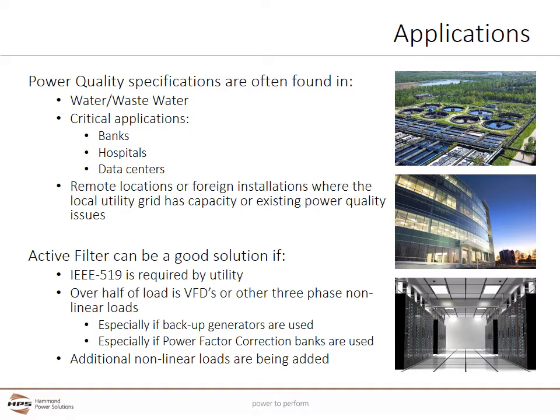Active harmonic filters can be a good solution and should be considered if any of these criteria are met: if IEEE 519 is required by the utility; if over half of the load is VFDs or other three-phase non-linear loads such as battery chargers; especially if backup generators or power factor correction capacitor banks are used; or if additional non-linear loads are being added.